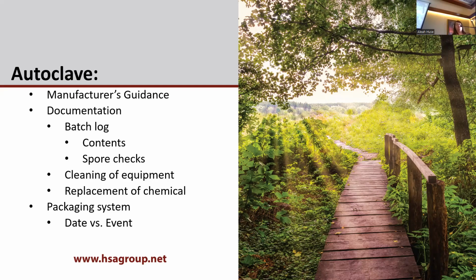So making sure you have your batch log, you know what contents were sterilized and when, you know the spore checks are being done according to manufacturer's timeline requirements. And then the other piece we find missing is documentation proving that you're cleaning the autoclave machine according to the timeline and manufacturer's guidance. Usually there's a monthly, weekly, daily, there's specific elements that you have to show you're doing within the autoclave, not just from the instrument process, but on the equipment itself. So making sure you have documentation of when you're changing chemicals, that the instruments are not sitting in that chemical longer than the 28 or 30 days allowed. You have date times of when that's being processed and changed.